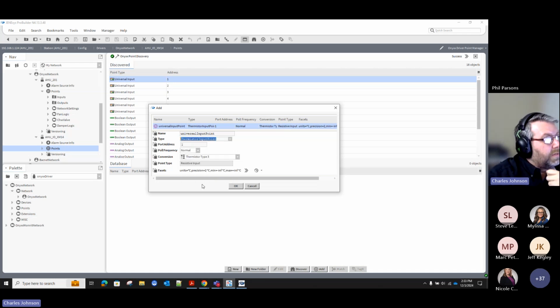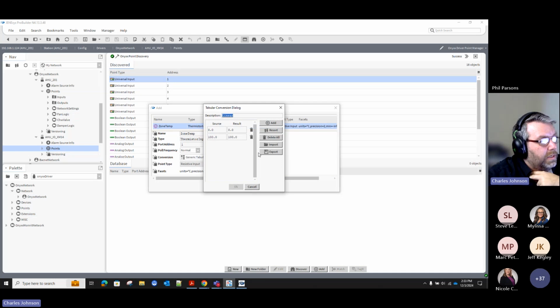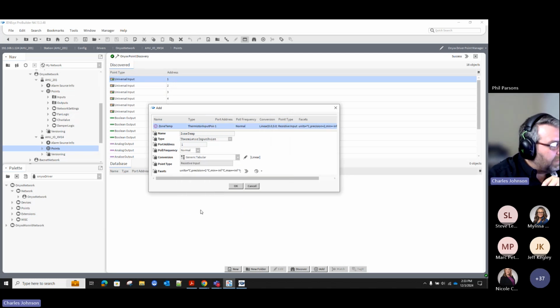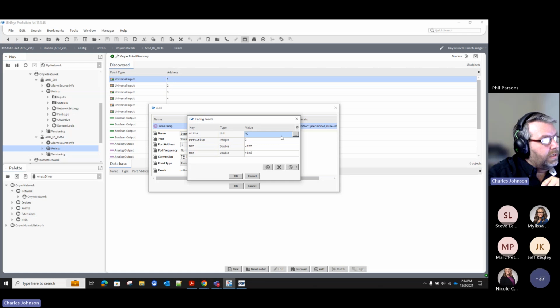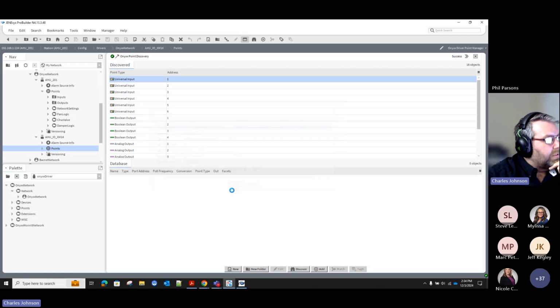I'm going to go ahead and show you a thermistor input here, and I'm going to name this zone temp. I can now change the facets, and as you can see here, we can change it to 10K type 3. If you need to do additional ones, we can do what we call a generic tabular view, which can give you additional results, where you can import your specific resistance and temperature if you'd like. But I'm going to stay with 10K type 3 here, and I'm just going to change the precision and units to degrees Fahrenheit with 1 unit of precision, and click OK.